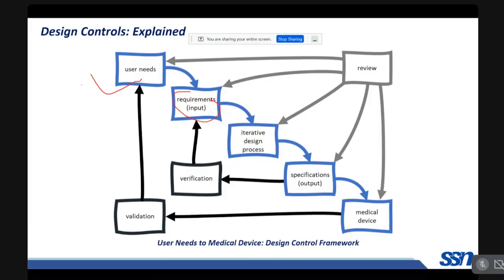First one. When it comes to the requirements, it is something like what the specifications for the medical device could be. In regulatory terms, we call them design inputs. Considering our example of a pulse oximeter, one of the design inputs or requirements could be that it should measure oxygen saturation with an accuracy of plus or minus 2%, and it must show the results within 5 seconds. And the pulse oximeter should fit the average adult finger. These are some of the parameters for design inputs.